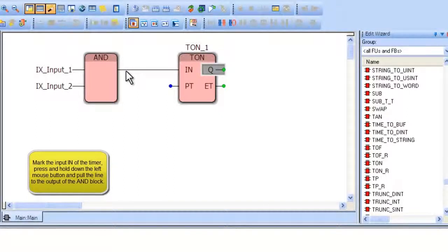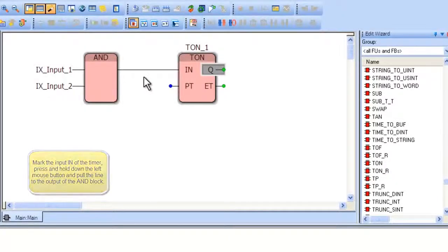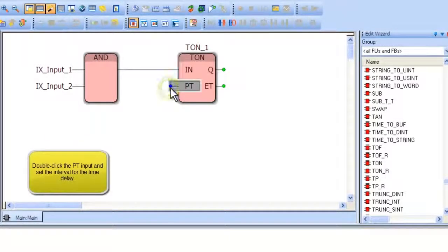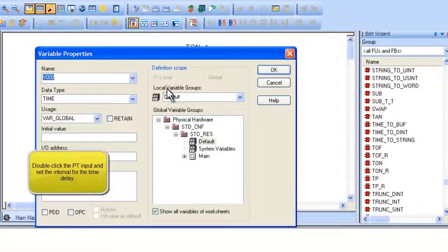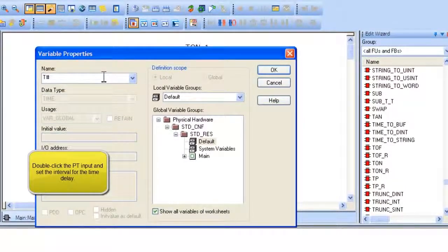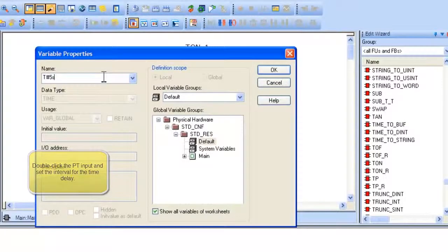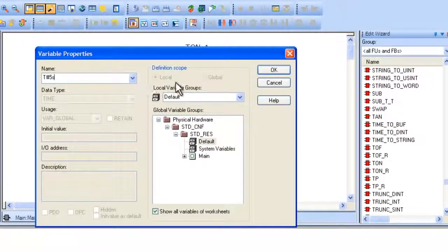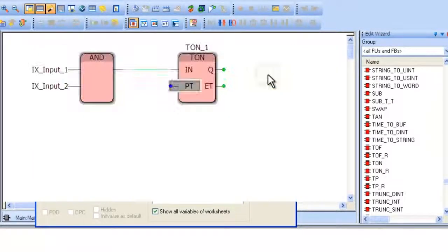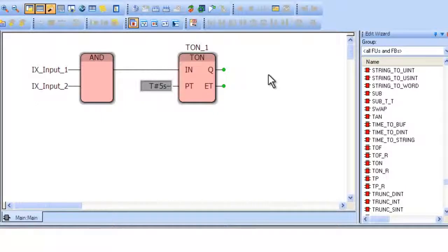Now to set the delay period, double-click on the PT input of the TON block. Name the variable T#5S. T# means time constant, and 5S stands for 5 seconds. This will implement a 5-second delay on the output of the TON block.